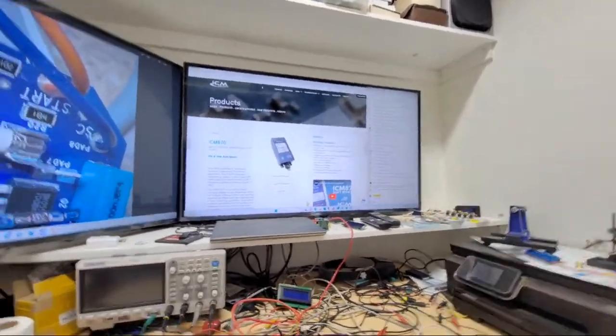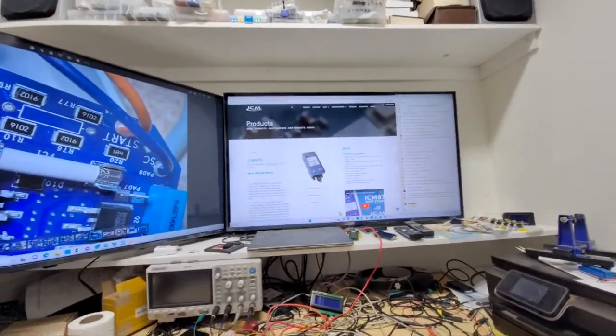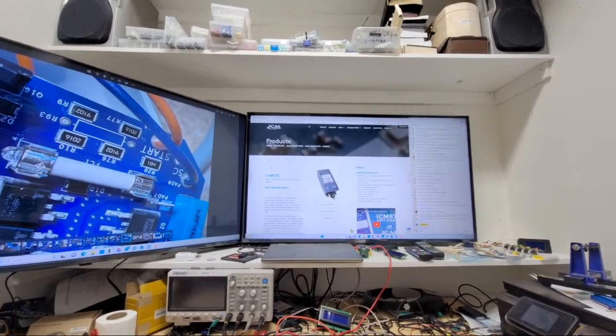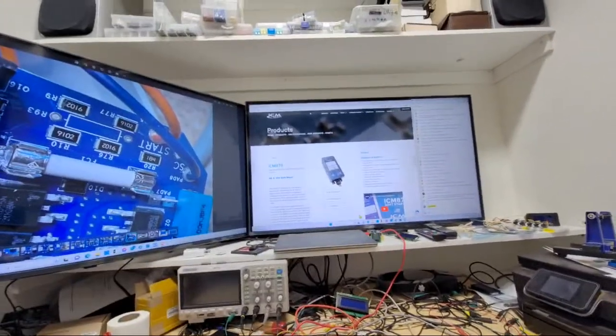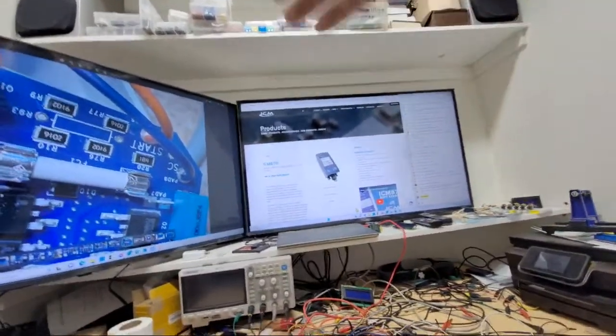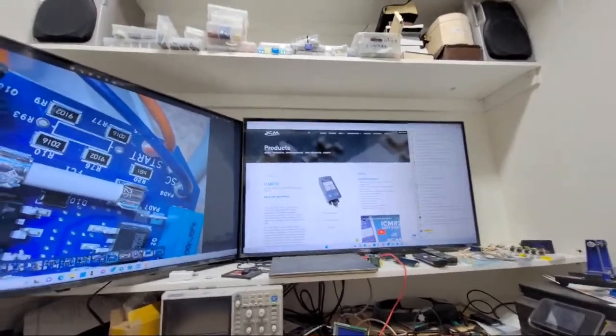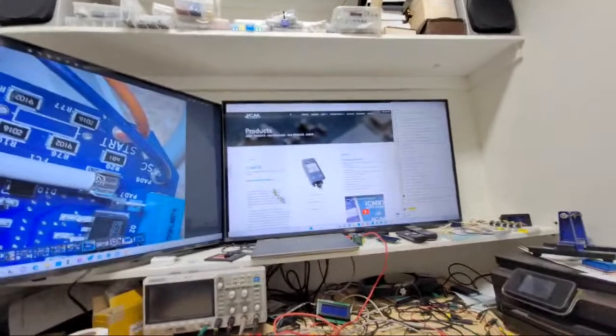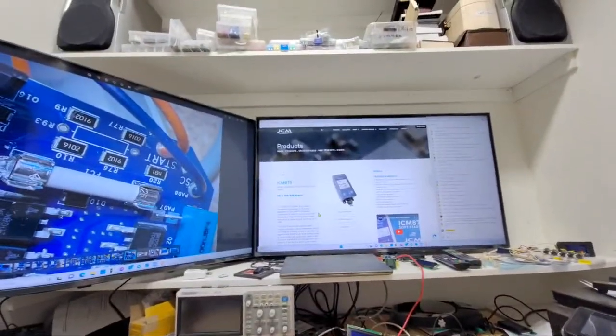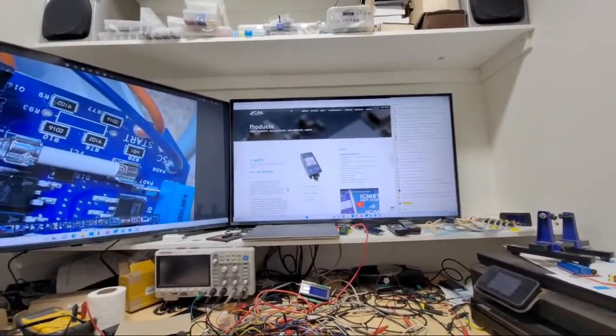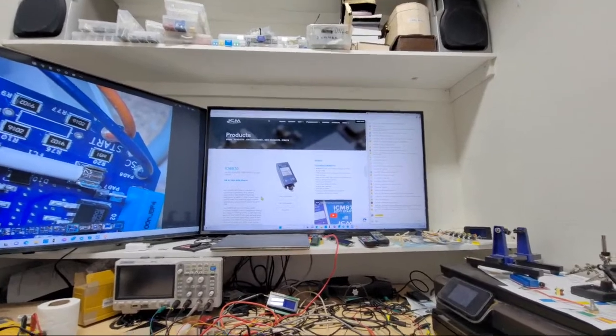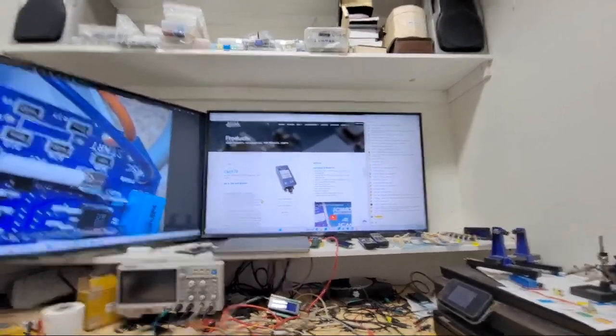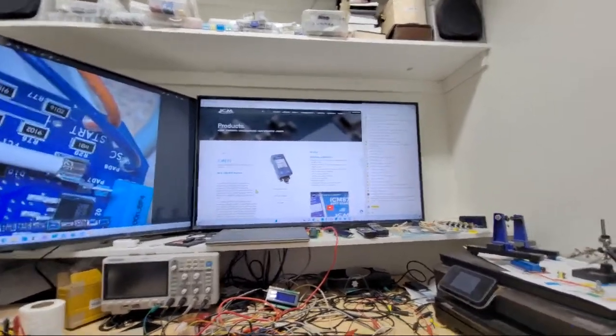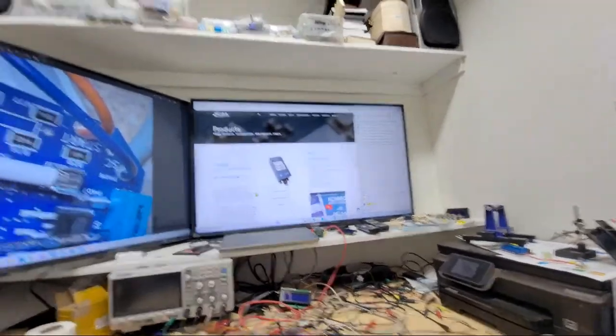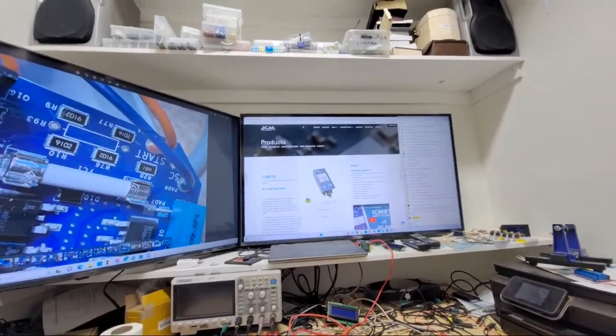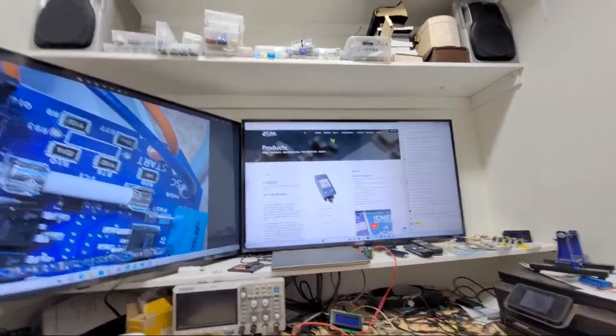But these things are going through and adding a delay - it seems like it just gets your outdoor fan motor started, and maybe your fan motors inside the house started, with the call for cool, and then 5 seconds later it closes the relay, adds the electronic means of the start capacitor, and gets your compressor started. Maybe somehow they're fine tuning the right amount of time for the start capacitor, because if you keep the start capacitor engaged too long, it also pulls crazy high amps. Anybody that's had a stuck potential relay will notice the compressor sounds really weird, and then it kicks out on an IP within another second or two - it definitely pulls some crazy amps if you don't take the start capacitor out fast enough. So these things could be fine tuning that and making it work. So it works, it's just not a soft start, that's all.